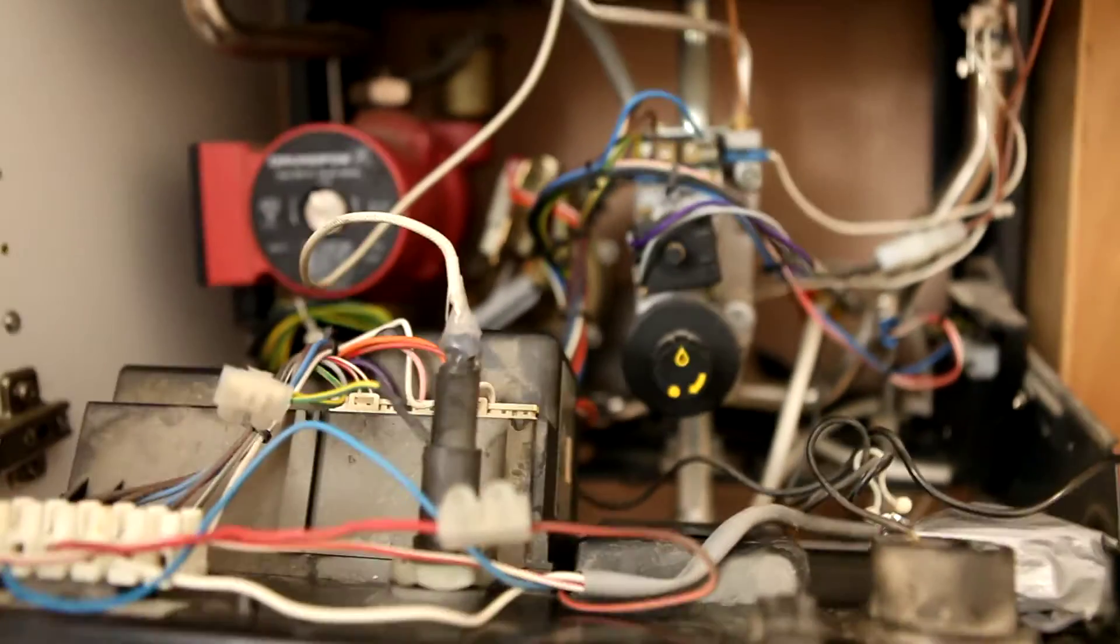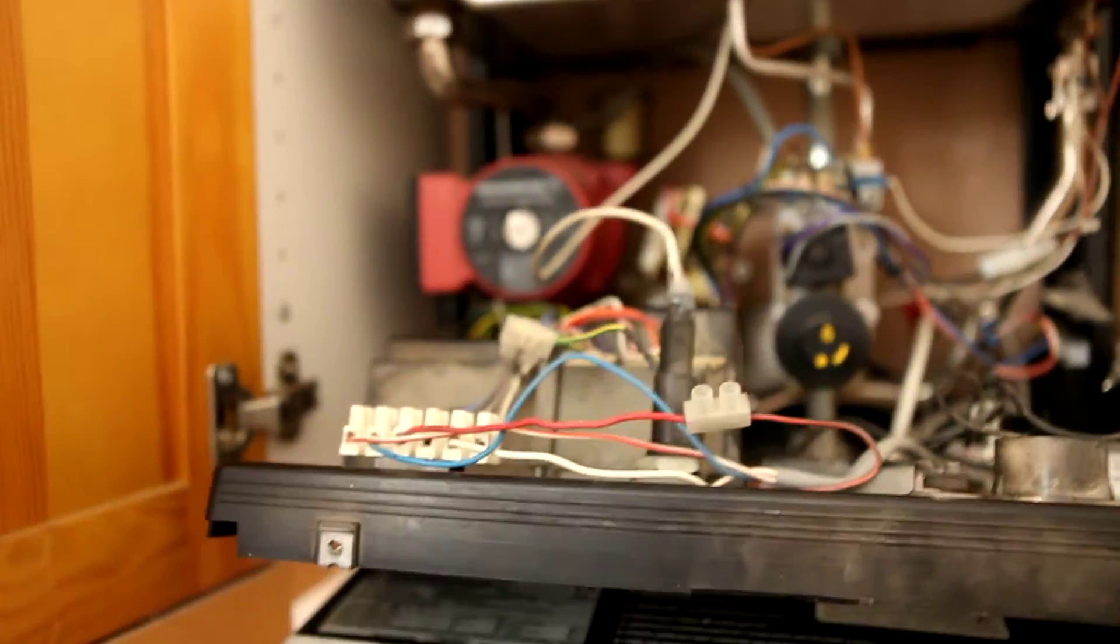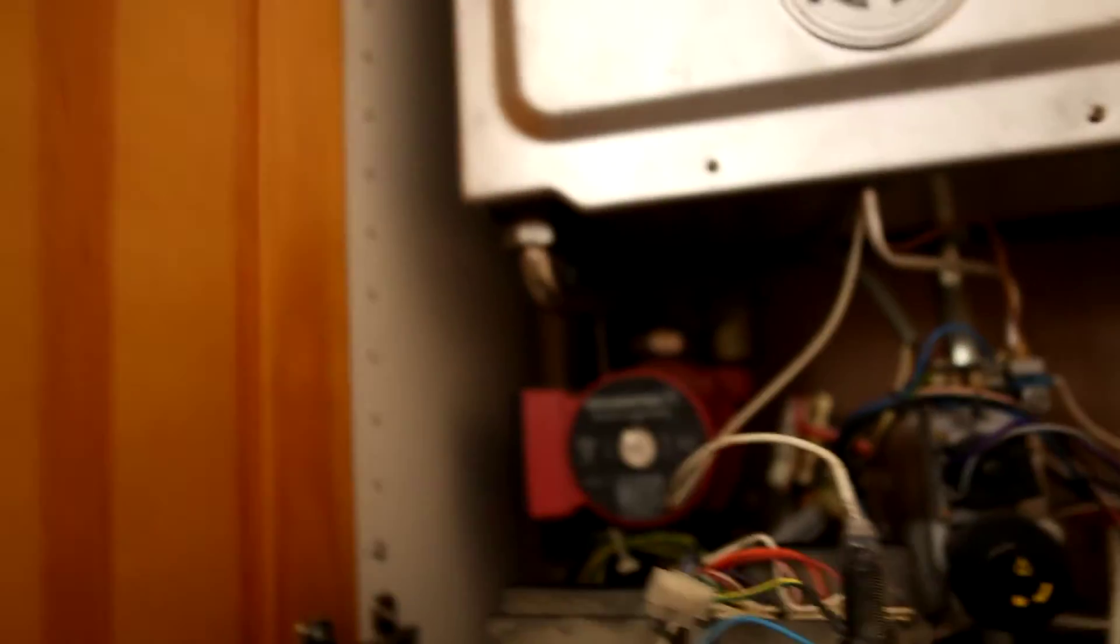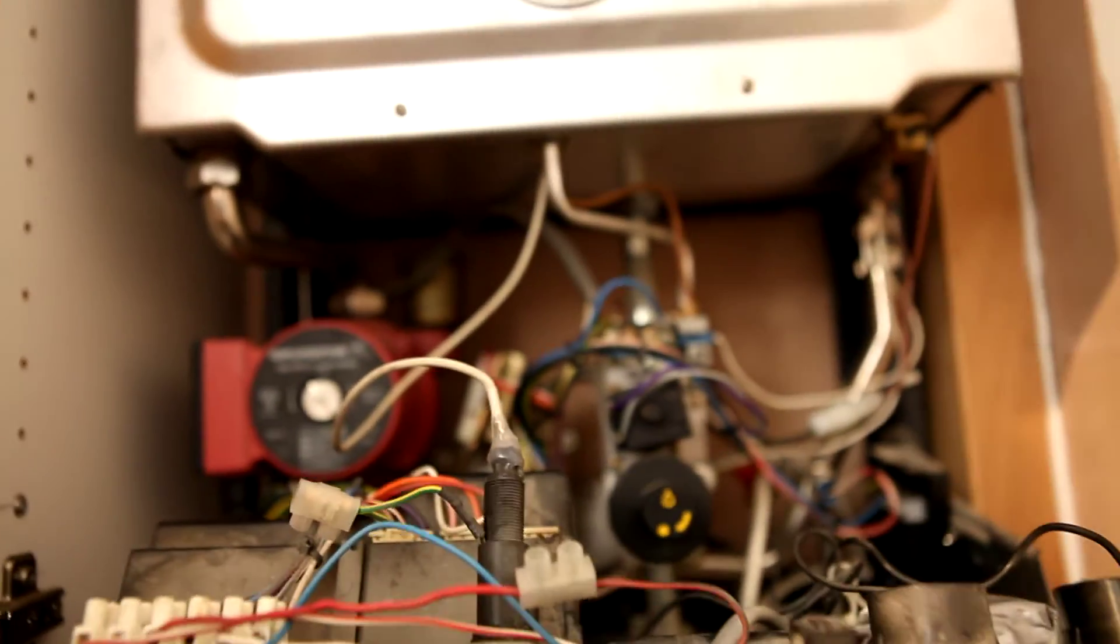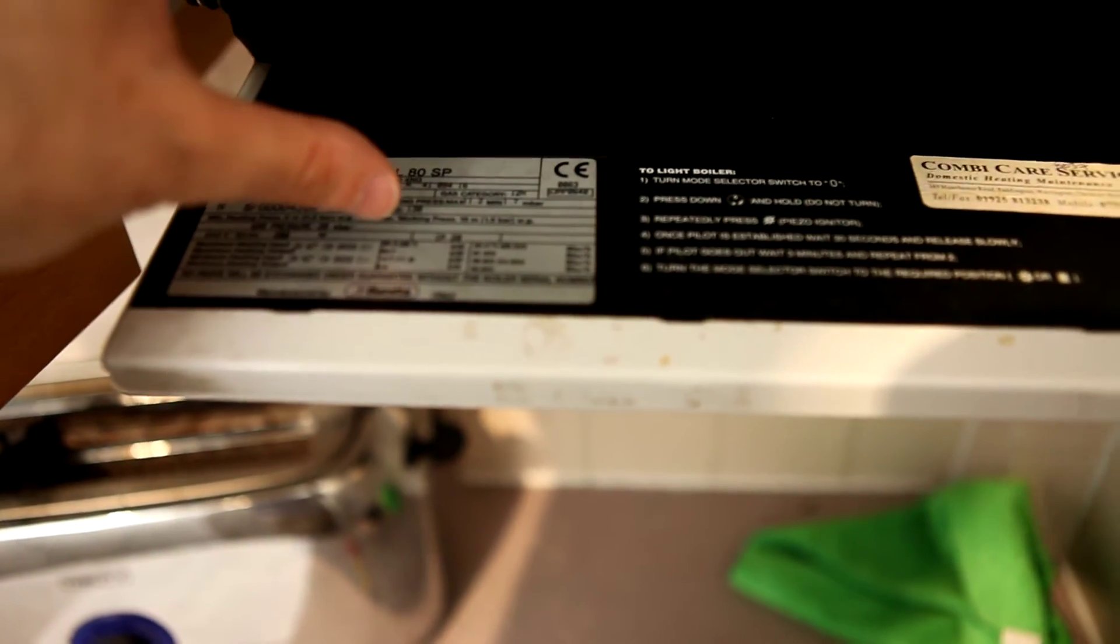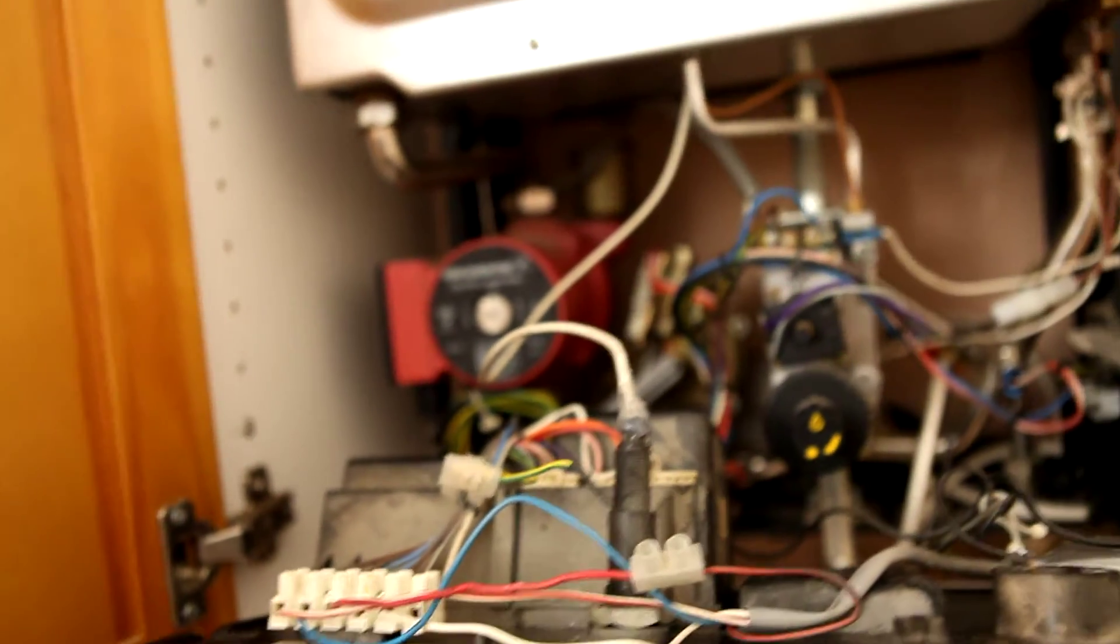I thought about this for a couple of minutes, and I thought, well, if the problem is the boiler's overheating because there's not enough flow rate, well surely then this boiler must have some way of correcting for it, and it does, because if we look at the nameplate here, you can actually see maximum power rating 29 kilowatts, minimum power rating 10 kilowatts. The boiler has the capability of reducing the gas pressure.